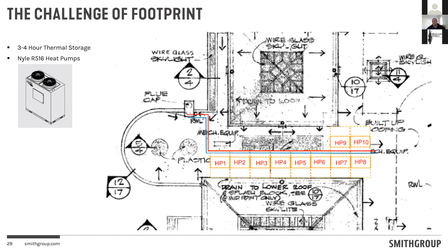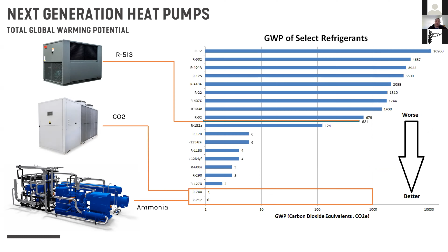One of the most exciting things that's just now getting onto the market and is actually available are commercial grade CO2 heat pumps. If any of you have done CO2 heat pumps in the past, they're typically targeted at domestic hot water systems because they need such a high lift. They want to take cold water and make it really hot. In field studies where folks have tried to do combo systems, they've really struggled on the space heating side because we don't see that big delta T on the water loop for space heating.